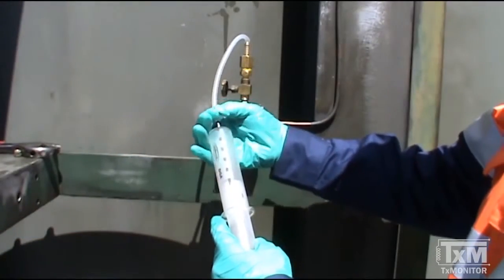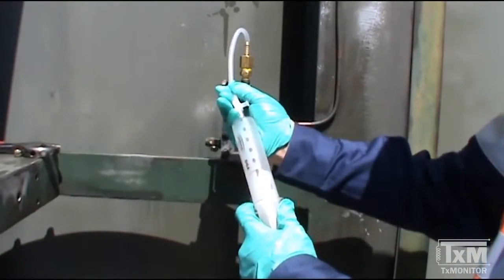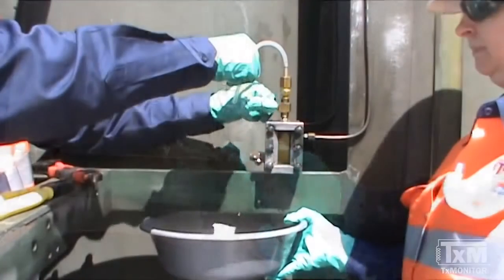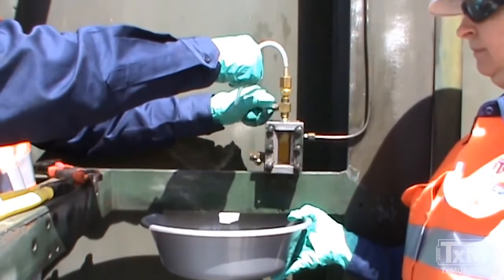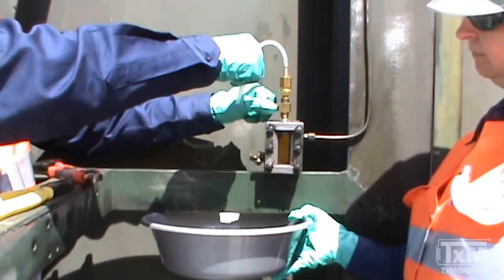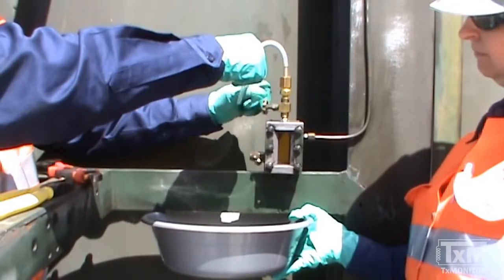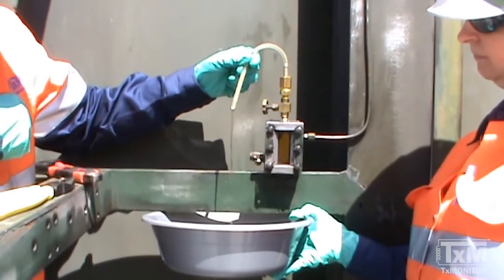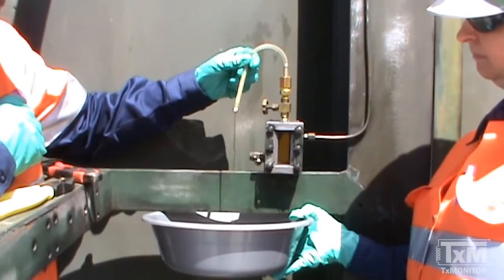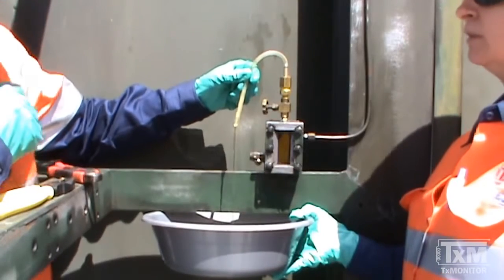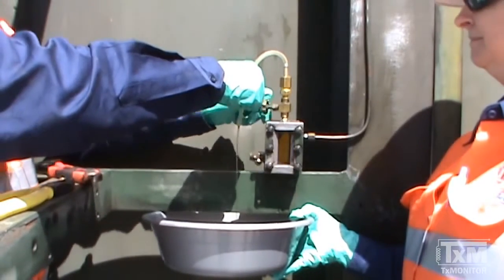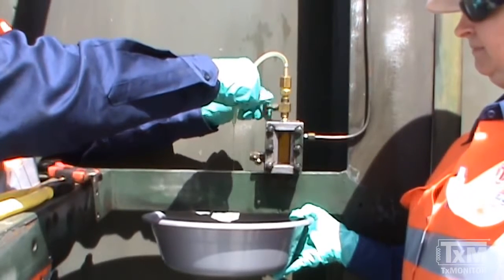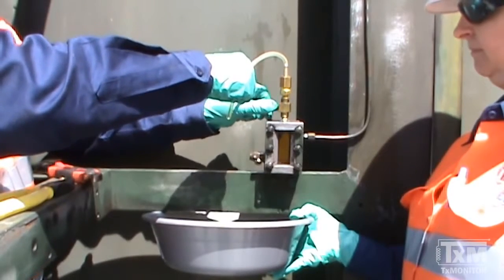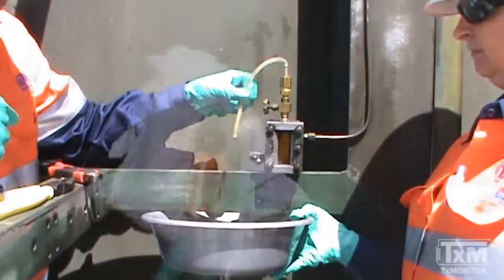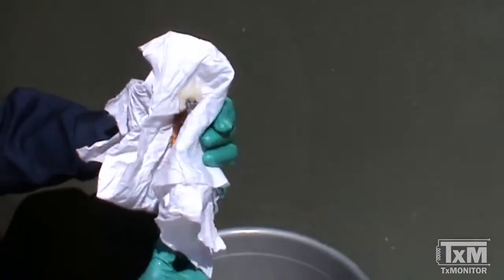When all the gas has been retrieved, ensure that the gas sampling device is purged by opening up the top port until oil pours out. If no further sampling is to be done, make sure all the valves are in the correct position, ensure all the plugs have been installed and tightened, and that the area and the sampling devices are clean.